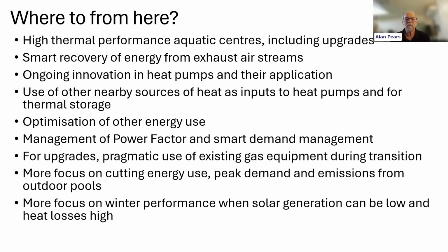We talked about management of power factor, which is effectively overheating of the electrical wiring and wasting electricity when the oscillation of the voltage and the current are not in the same phase. That can be very significant. When people are worried about having to upgrade electrical supply capacity, if your power factor is poor, really focusing on it is one way you may be able to avoid or reduce the need to upgrade your electrical supply system. There's lots of equipment available to do that.